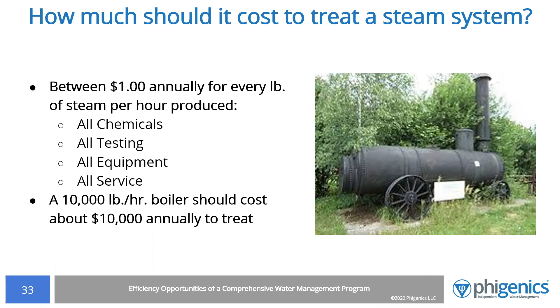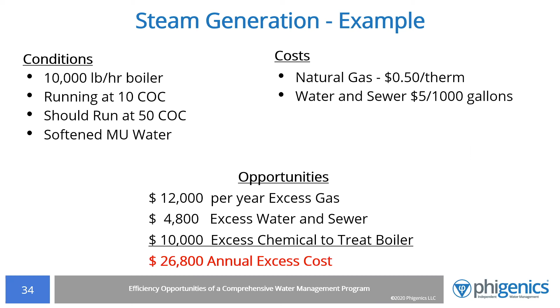Here's an example of a very simple boiler with average costs running at 10 cycles of concentration, which is more typical than you would think. In most situations, you should be able to raise the cycles of concentration to 50. Doing so results in savings of over $26,000 per year. Multiply that by several boilers or larger boilers, and pretty soon you are talking about some serious cost savings, all without jeopardizing your equipment.